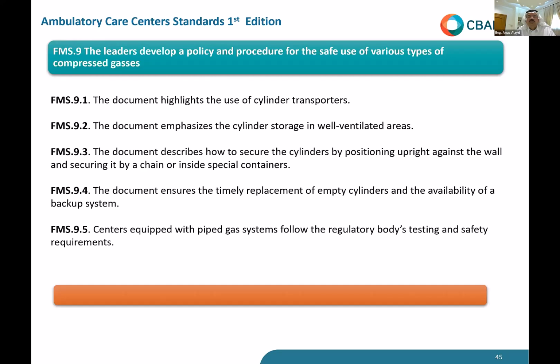The document ensures the timely replacement of empty cylinders and the availability of a backup system. If you are using cylinders, we don't want the nurse in the ER asking for cylinders and the administrator saying, oh, sorry, we have no oxygen. No, we can't do that. You have to make sure you have a backup and you are refilling in a timely manner. This is what we want to check, and it should be documented. When we come to you, we want to see that it is available there.